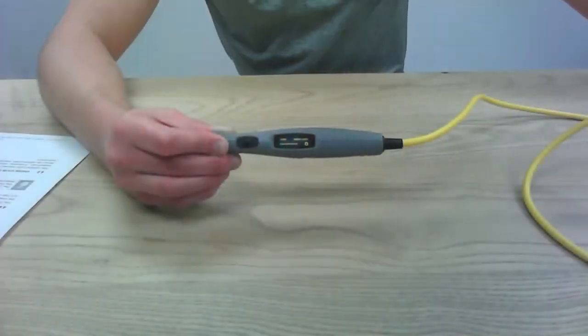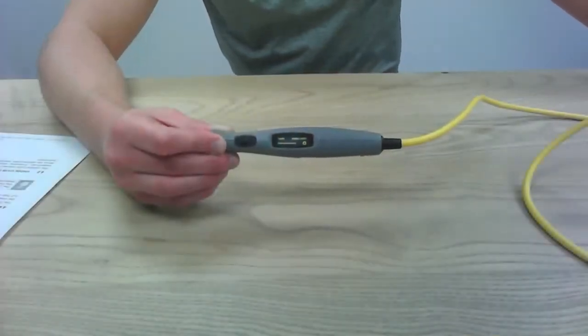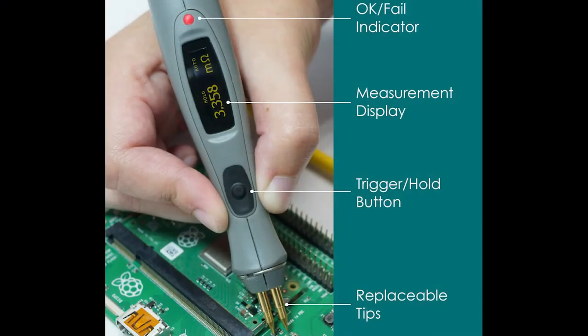The 710A display probe is made up of three main parts. The OLED display, which has indicators for your resistance measurement, if you're under or over range, open lead detection status, and hold status. Your remote hold button, which functions just like the hold button on the 710A. And your pass-fail LED, which will light green if the measurement is below the test limit and red if the measurement is above the test limit. We'll go over that in a little bit.